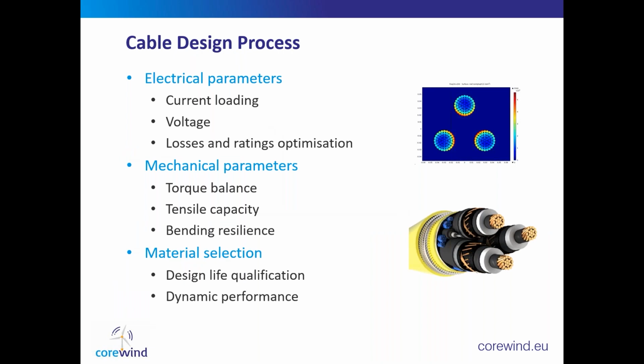A similar process for the cable configuration, though here we start with the cable design, its electrical parameters, the current loading on the basis of the number of turbines for which each cable will be carrying current, the voltage of the system, and consideration of the electrical losses, the thermal losses, and optimization of the size of the cable on the ratings. Mechanical parameters that need to be considered for dynamic cables include torque balance, the tensile capacity for installation of these long lengths of cable in deeper waters, and resilience to bending loads. This will infer the material selection, as well as the requirements for design life and the cable's dynamic performance.